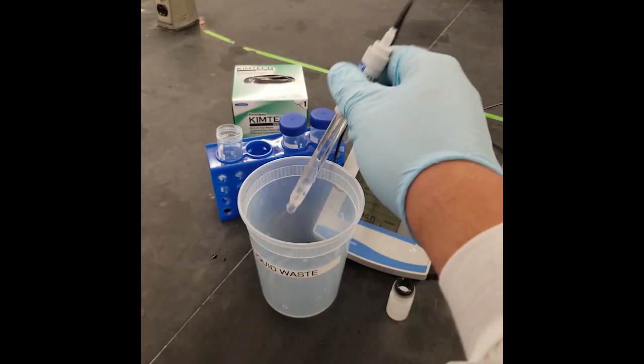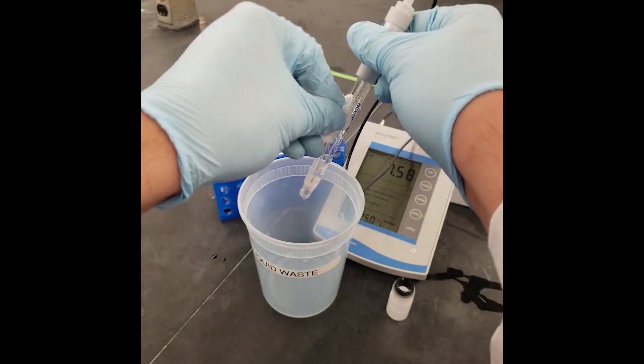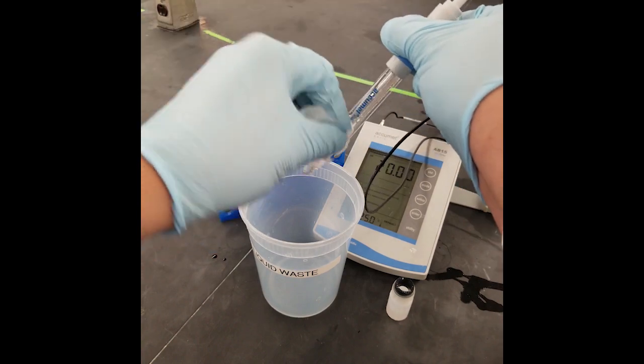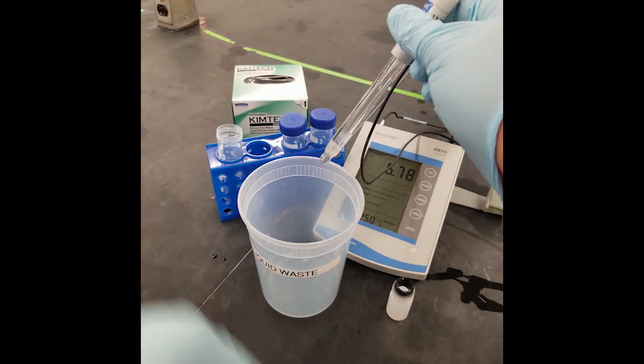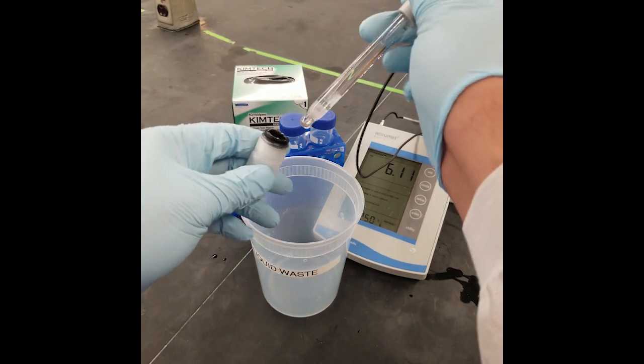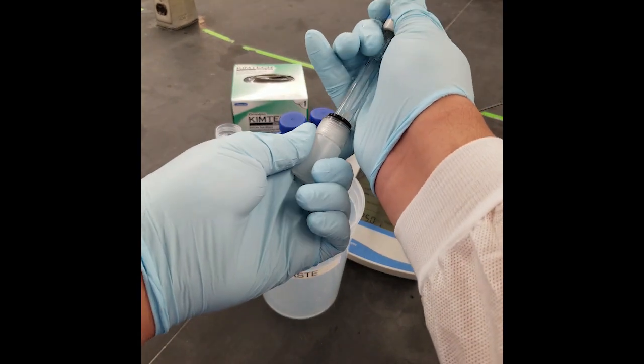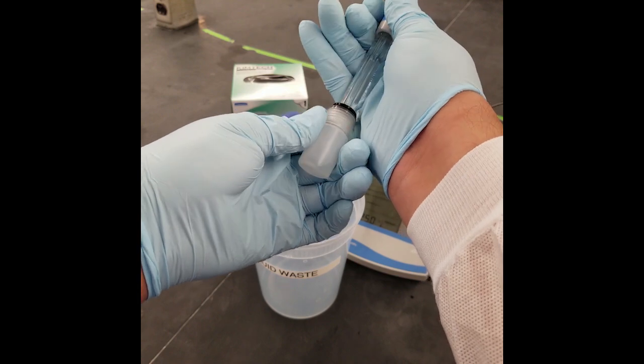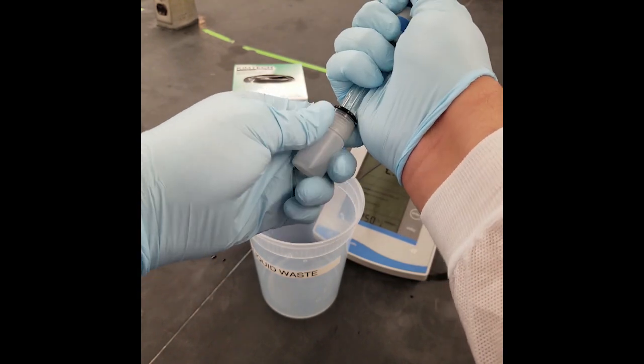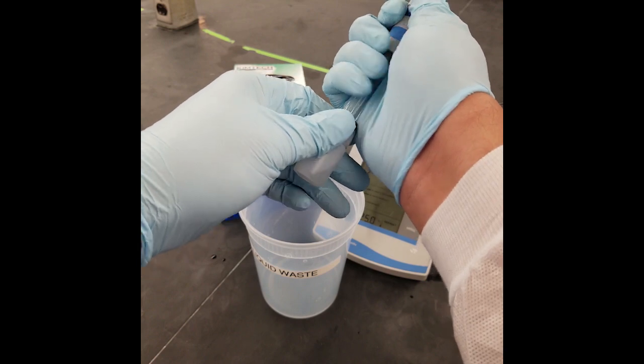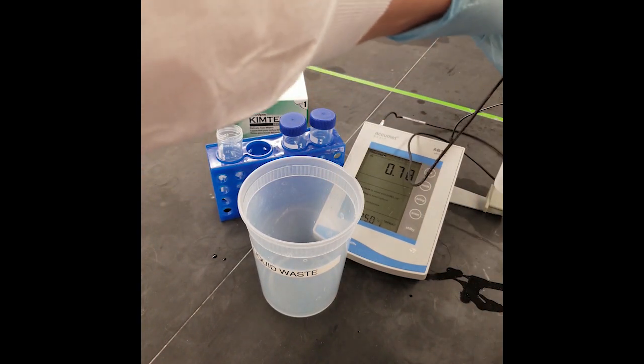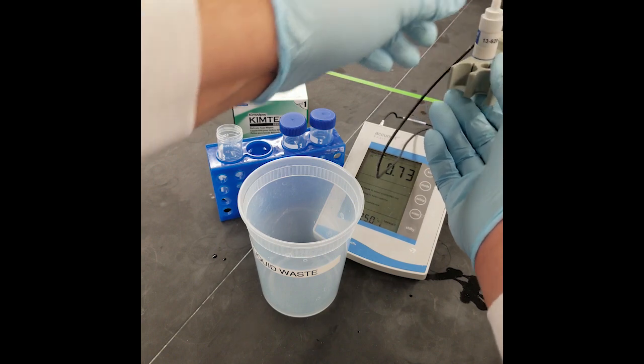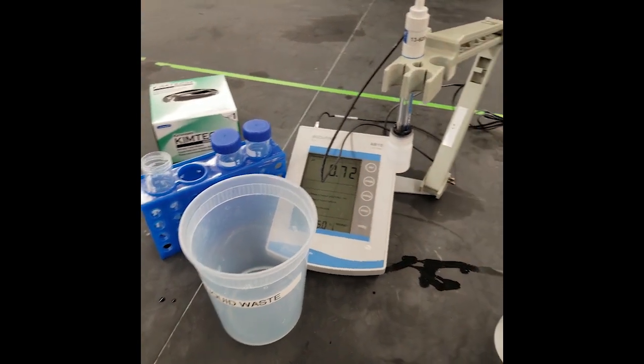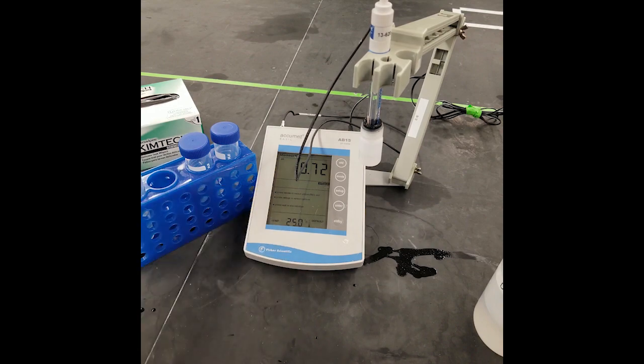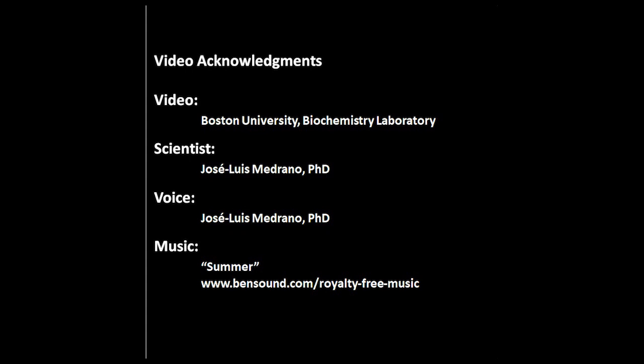Make sure to dab it dry so that you don't change the concentration or the composition of the storage solution. And then as gently as possible, go ahead and insert the probe back into the storage solution. You don't want to put too much force on this because the end of the probe is delicate, and even though the storage container is plastic, you don't want to accidentally shatter the tip of the probe. Call over your teaching fellow if you want to get a check that you did everything correctly, and then it goes back onto the adjustable arm, and you're pretty much done for your entire experiments.